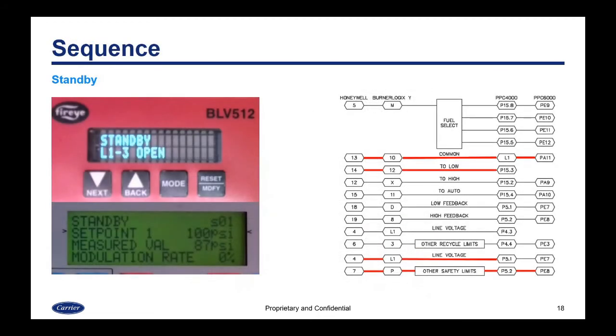Now we're going to go through a sequence showing in red which terminals are activated so we can see what's going on. So here we're in standby. In standby, you're going to have voltage to the low terminal. It's got to have voltage on one of the three terminals at all times, so it's going to be to low. And our safety limit string is going to be complete. So this is where we're at in standby.